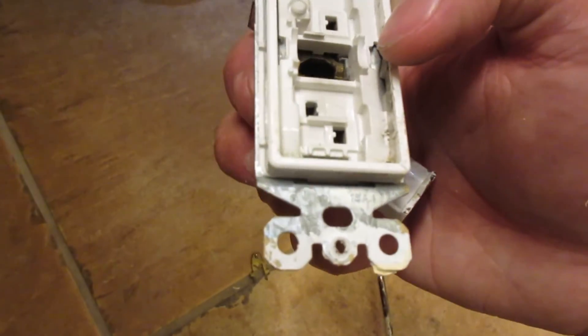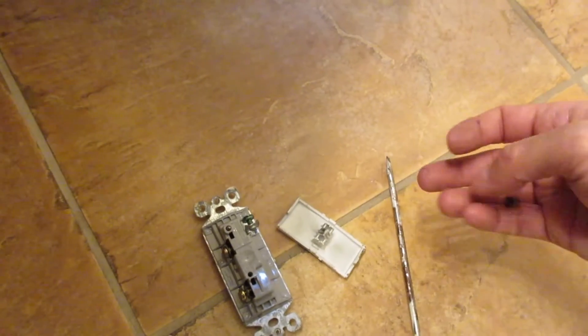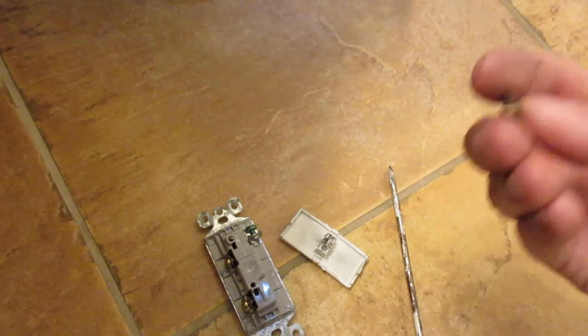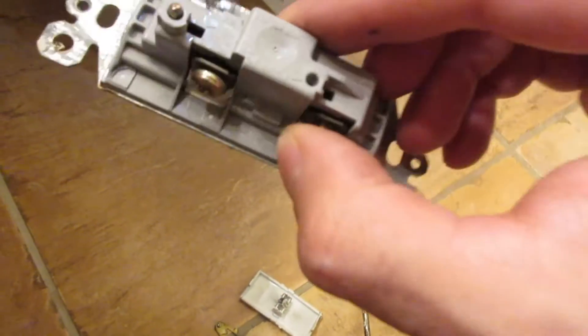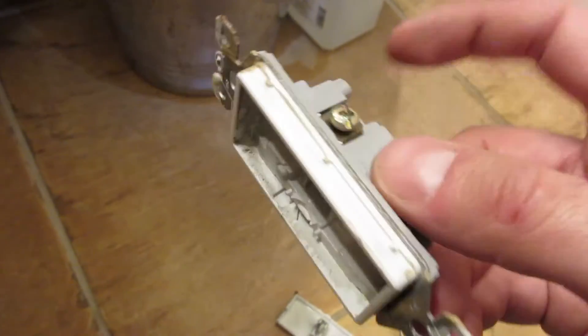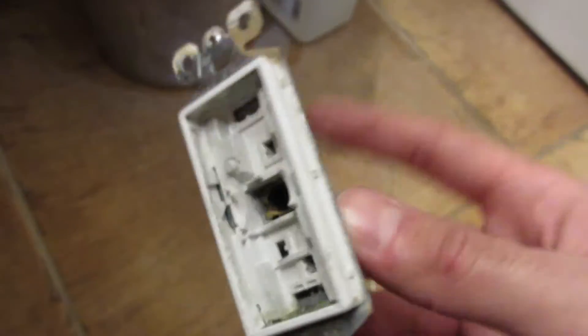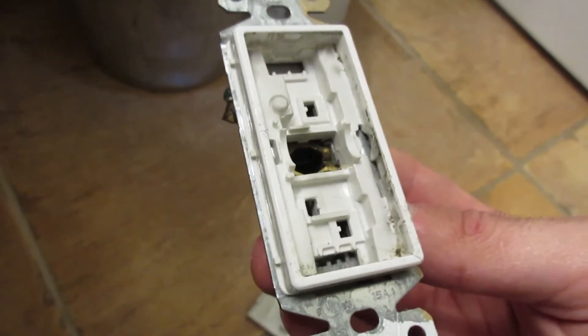The outlets suck too. I got a cool electrical tool because you gotta play with electric so much — certified electrician by the way. They have problems with that too. They used to get bad contacts with the push-in, so you had to use the side terminals because these ones wouldn't make contact. And they painted the wires too, then stuck the wires in — so you won't get a good contact. Just fucking ridiculous.